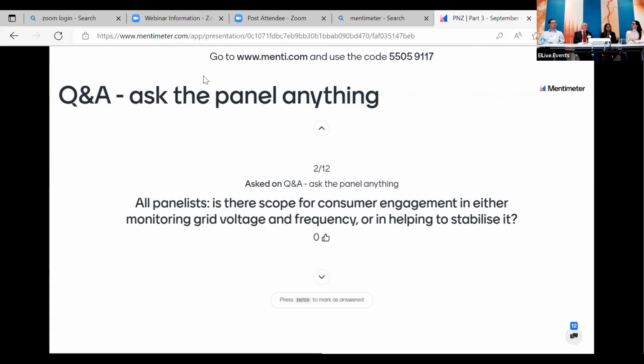However, recently, after a lot of discussion and hard work on the part of ESO, OEMs, and developers, something called the grid forming converter has been introduced. I would hate to say it replicates the synchronous generator, because it doesn't. A grid forming converter can be 100 different things. It pretty much tries to hold on to a reference and help grid stability by either adding voltage stiffness or providing inertial response. So instead of providing direct inertia, it provides something called inertial response, which is a fast injection of power to control the drop of frequency, just as inertia would do—it's kind of simulating inertial behavior.